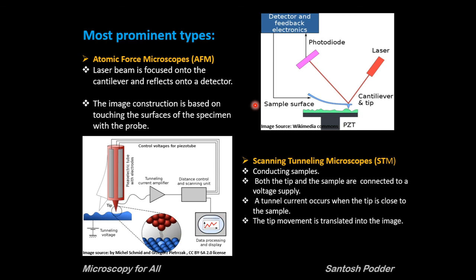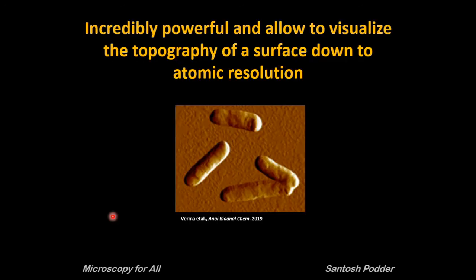The second type of scanning probe microscope is the scanning tunneling microscope (STM). In this system, the main limitation is that only conducting samples can be used. Both the tip and the sample are connected to a voltage supply, and a tunnel current occurs when the tip is close to the sample — the tip movement is then translated into an image. Using scanning probe microscopy, we can visualize the topography of a surface down to atomic resolution — these microscopes are incredibly powerful. Here you can see an image of Mycobacterium taken using an atomic force microscope.